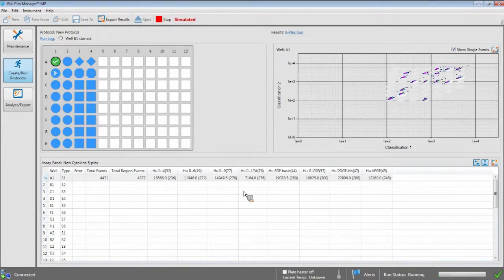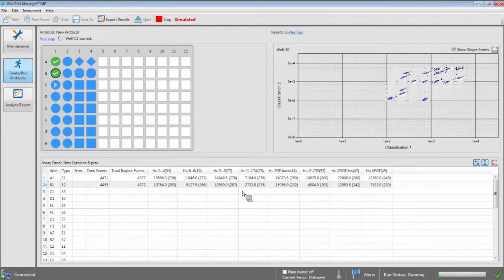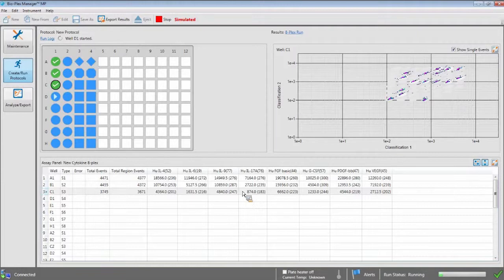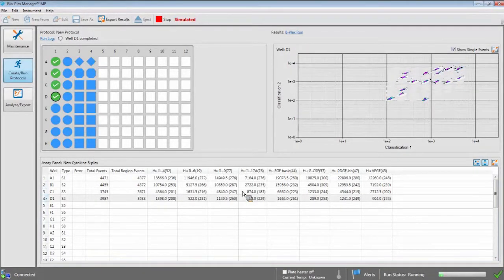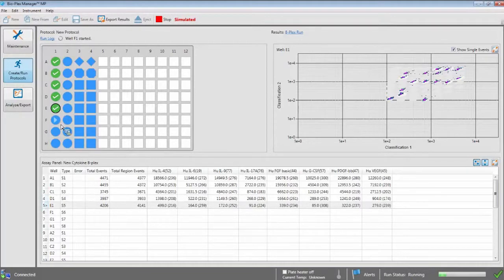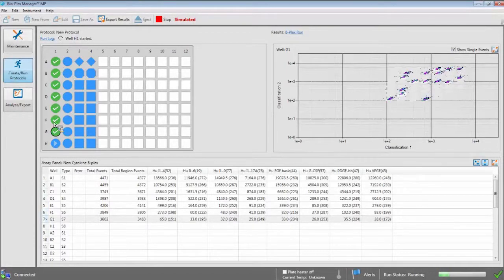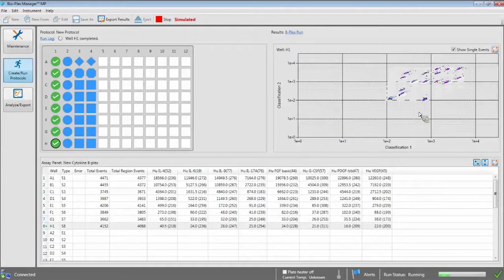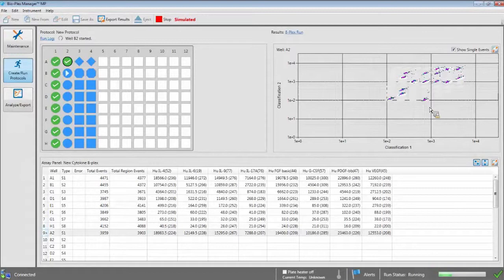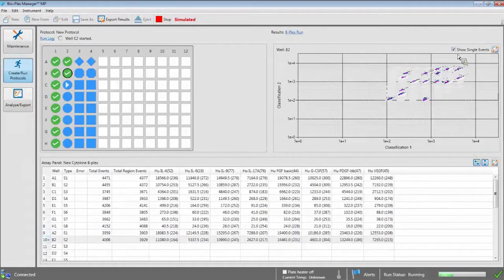Since this is an emulation, the data collection is faster than it will be with an actual plate. As the MagPix starts collecting data, you can monitor the data as it is collected. In the plate setup, it will show you which wells have already been read as well as the well that is currently being read — the current well will have a flashing triangle in it. Wells that have already been read will be green to indicate data was collected without problems, or yellow to indicate a problem such as low bead count. On the bead map, you can watch as events are collected in each region, giving you a quick visual confirmation that beads are being read and falling into the correct regions. There is a check box that lets you toggle between seeing single events or all events.